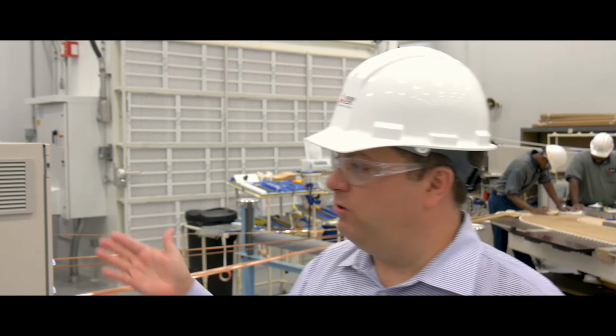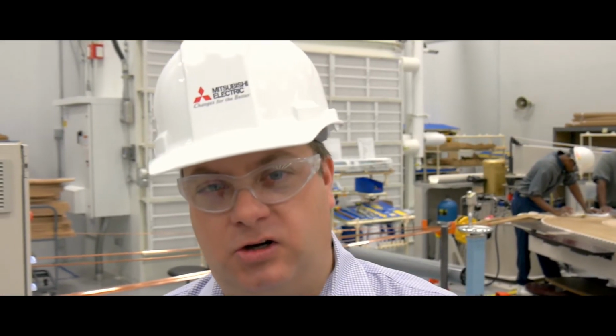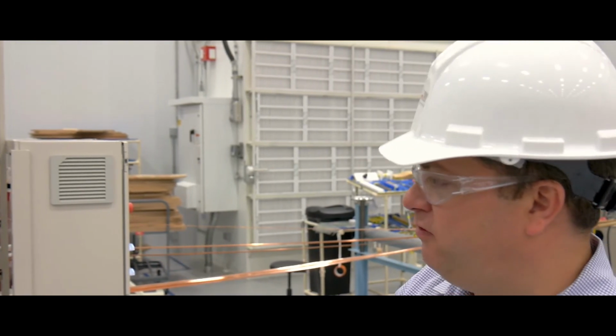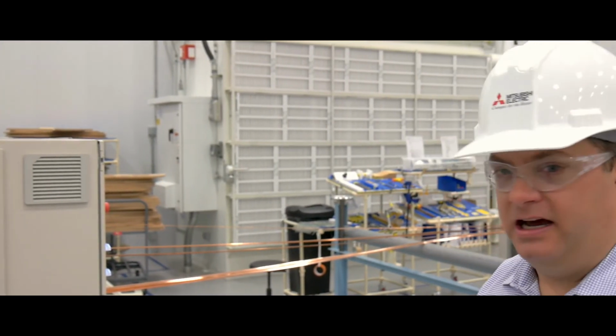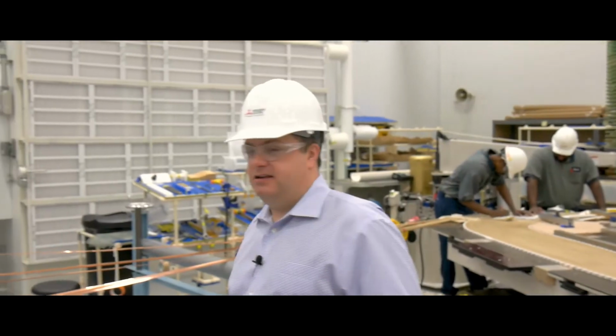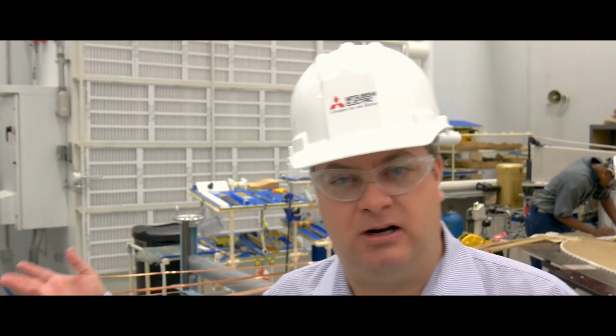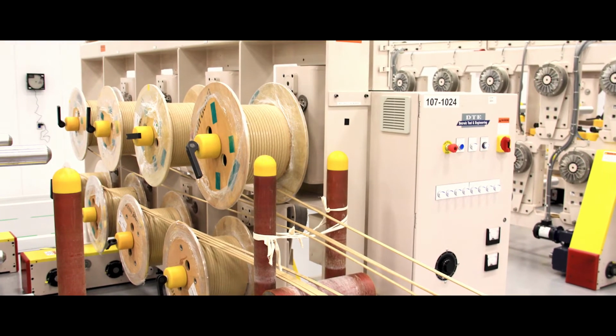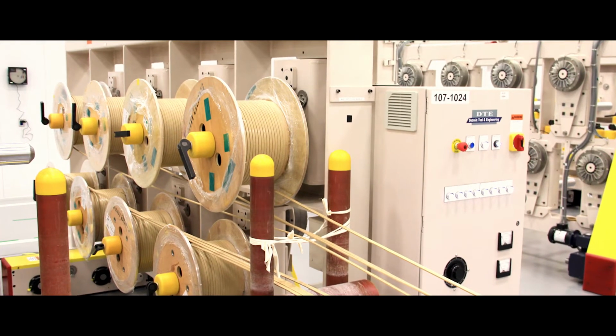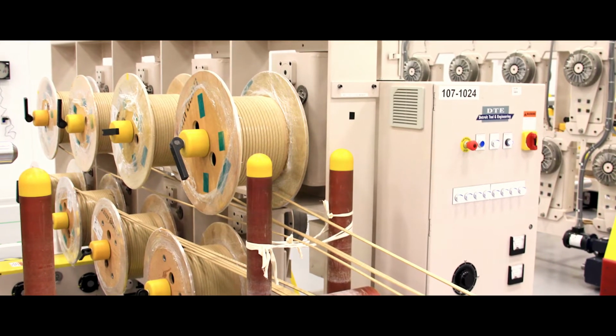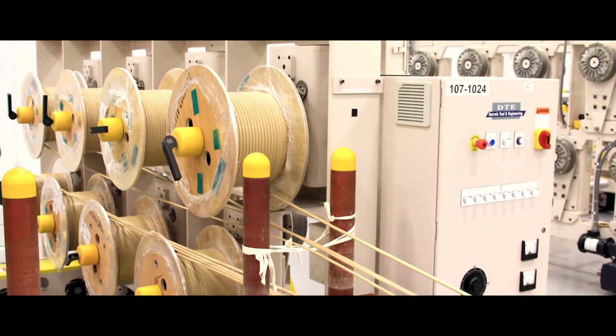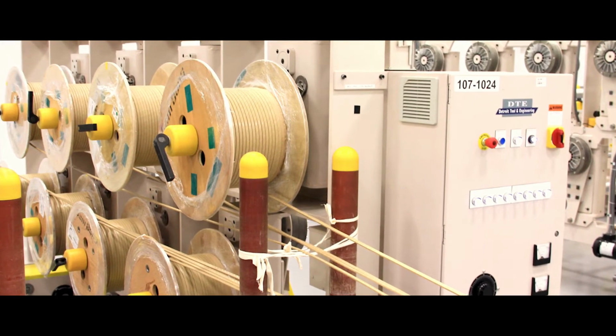The first step is receiving the individual conductors we use to wind the coils. We purchase those pre-wrapped from our supplier. This machine is what we refer to as a reel stand. It holds the individual conductors and keeps tension on them as we wind them into a coil, helping with the overall dimensional stability of the coils as they're being wound.